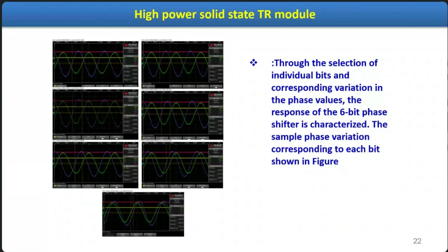If you put 1 bit, it will give a 5.2 degree phase shift. Suppose you use the second bit, it will activate 11.50 degrees. Like that, up to FF value, then it makes it 0 again. This is the phase shifter configuration. The phase shifter itself comes as one PCB, a 6 bit phase shifter.